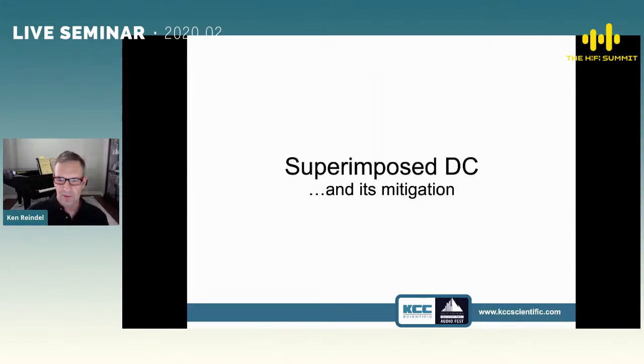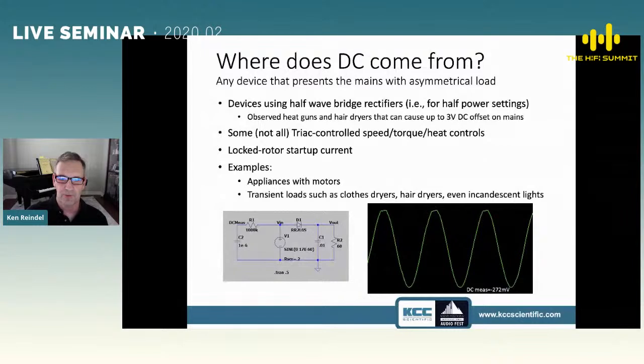Okay, so let's talk a little bit about superimposed DC and how it's mitigated. This comes up periodically, and it's a real important one. The first question is, we're talking about AC line here, so where in the world is DC coming from? We're not batteries in series with our power line, hopefully. So what's going on? Well, it's more common than you might think, and it's caused when any device plugged in somewhere on that line, or even in the same locale, presents an asymmetrical load. In other words, one half of the sine wave is loaded more than the other half.